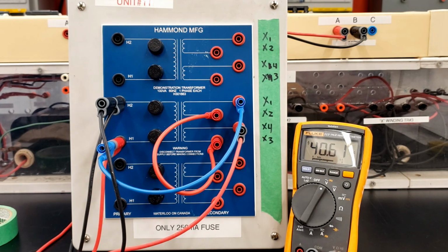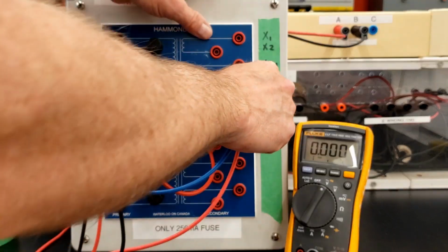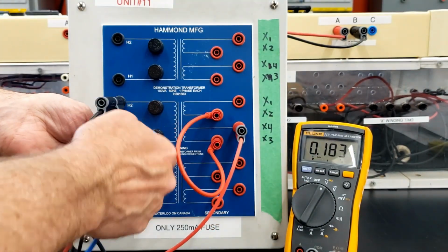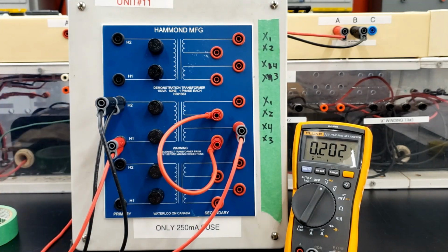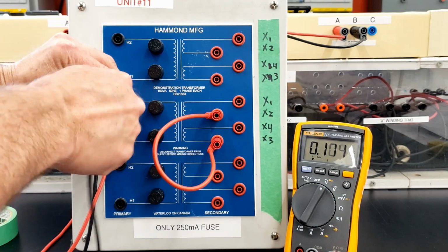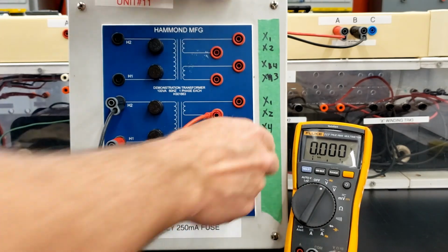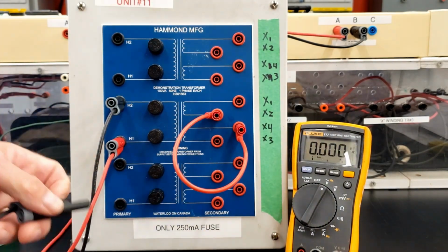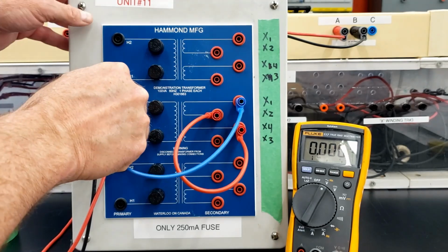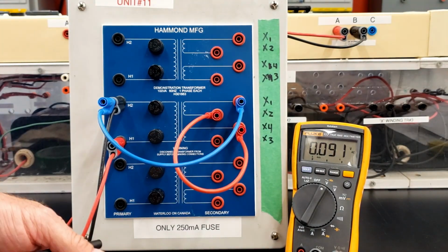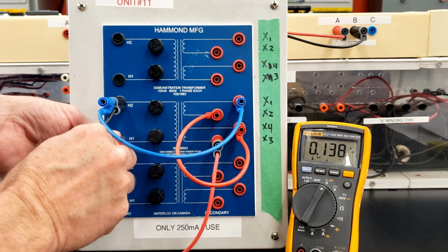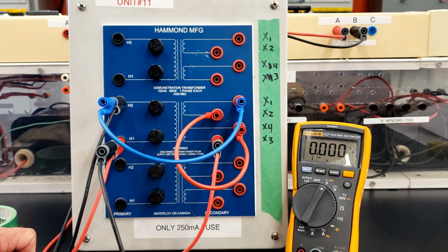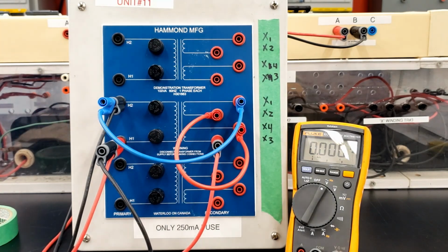Nice. Okay, if we had screwed this up, let's show that one more time. Just taking all my connections out for the meter, I would have thought this was 3, like I did before, right? So if that's the case, and I go back to the additive voltage, H2 to X1, then when I take this voltage between the two open terminals, these two voltages are going to cancel out, and I'm going to be left with the voltage of the supply on the primary.